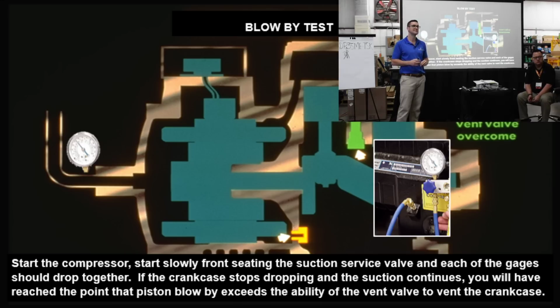So you have more than one problem though, because now you had bad oil return, which caused your pistons to wear. Oh, no, it wasn't bad oil return. What was the cause of that blow-by? What caused the wear of the walls and the rings? Was that flood valve? Overheating. Thank you. So that overheating, the lubrication properties got too hot. The oil got hot, it can't lubricate now. Oh, I get it. Okay.